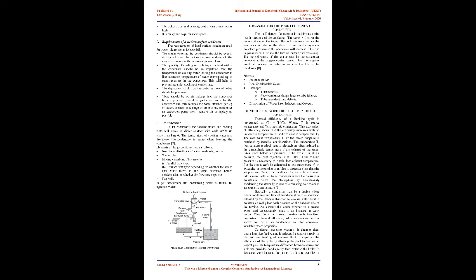The deposition of dirt on the outer surface of tubes should be prevented. There should be no air leakage into the condenser because the presence of air destroys the vacuum within the condenser and thus reduces the work obtained per kg of steam. If there is leakage of air into the condenser, the air extraction pump should remove air as rapidly as possible.